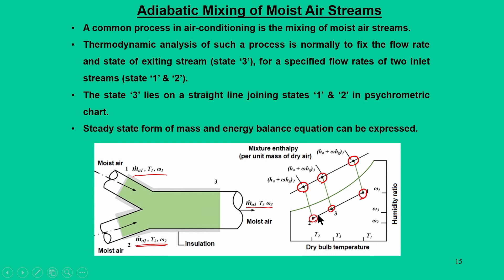So, the mass balance equation we can write as m dot A1 plus m dot A2 is equal to m dot A3, and that is for dry air. For moist air we can introduce the humidity ratio omega, which correlates the mass of water vapor with the mass of dry air. From then we can also do the mass balance equation for water vapor. When you do this, we finally land on an equation which involves the ratio of m dot a1 by m dot a2, which is equal to omega 3 minus omega 2 divided by omega 1 minus omega 3.